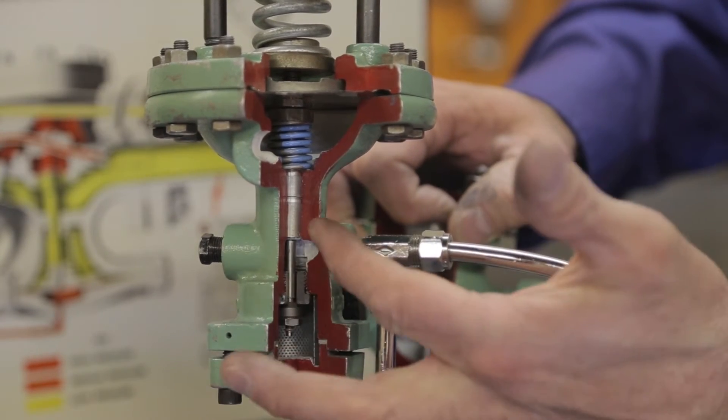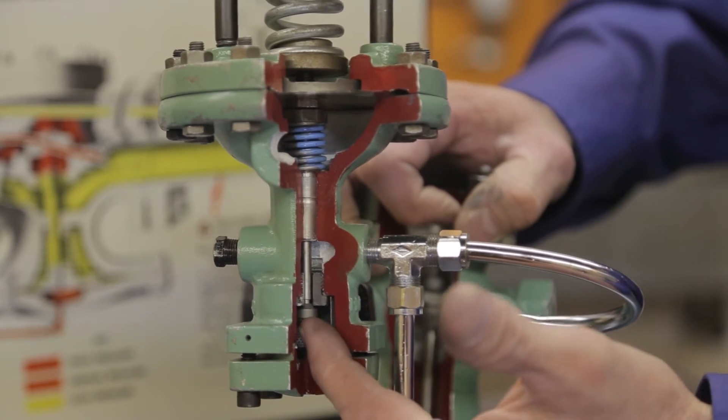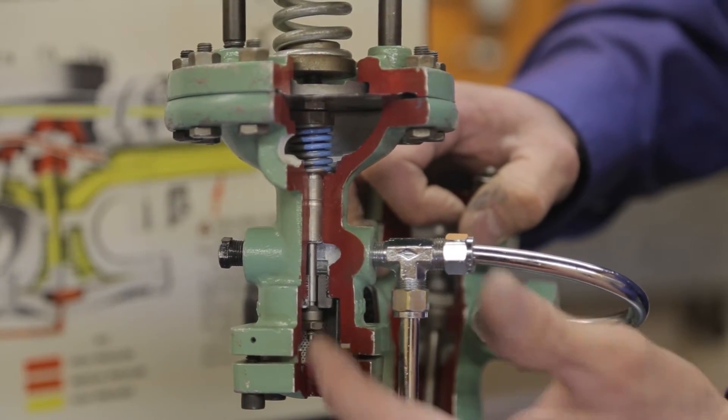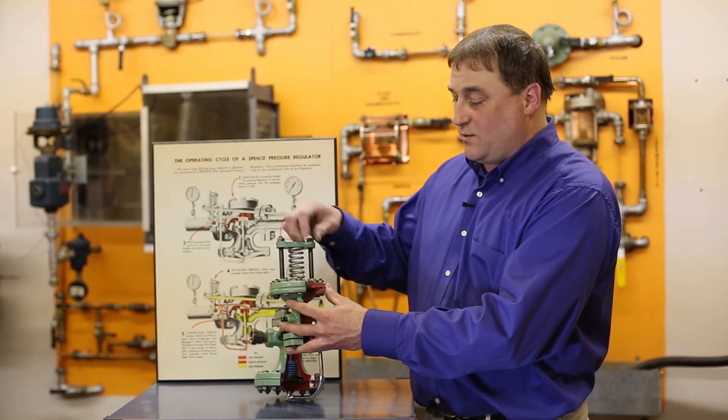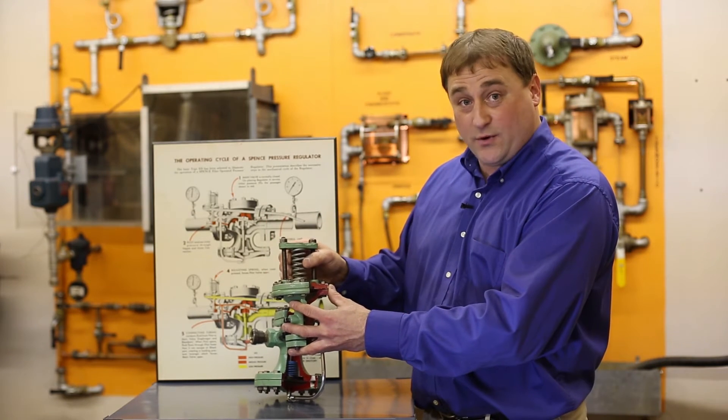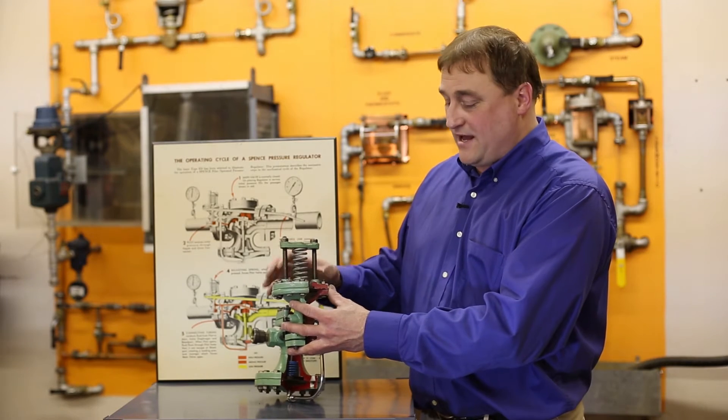This area is connected via the delivery line or sensing line that ties into the downstream side that we're trying to control. The tighter that we adjust these nuts, the more spring force they put down on the valve.